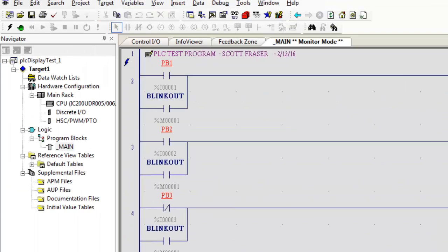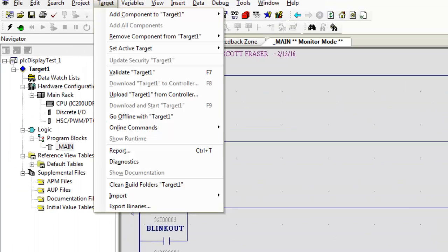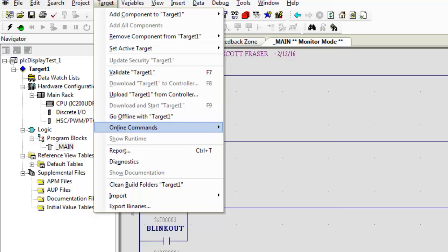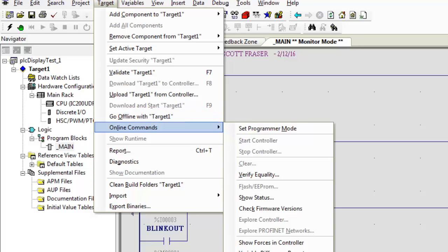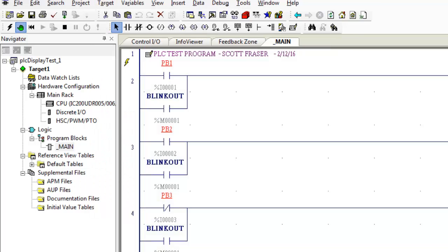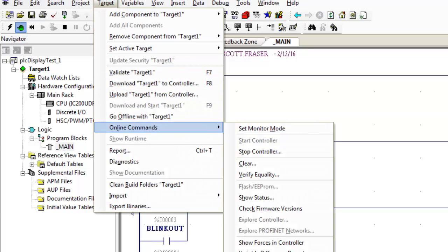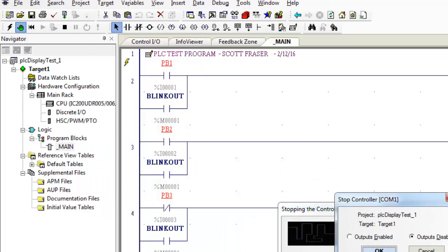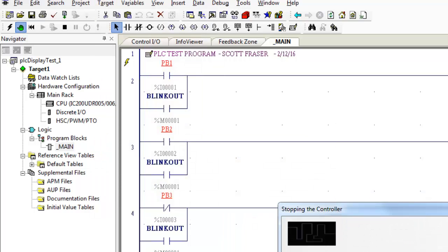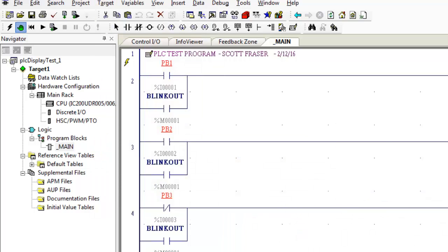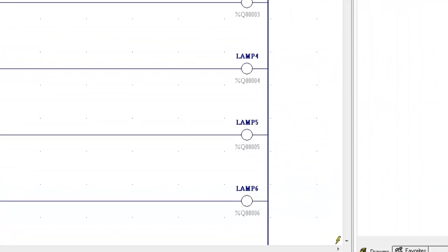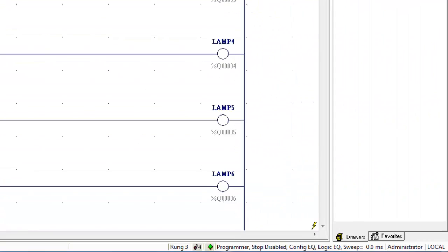And it's also in run mode. So I'm going to come up here to target, online commands and set the programmer mode. Again target, online commands, stop the controller. Remember we cannot give the PLC new commands while it's heading down the road. We have to stop it first. Now I look down here we're in programmer mode. Stop disabled mode. Configuration equal and logic equal. Yours will probably say NE. And sweep times zero milliseconds meaning it's stopped.